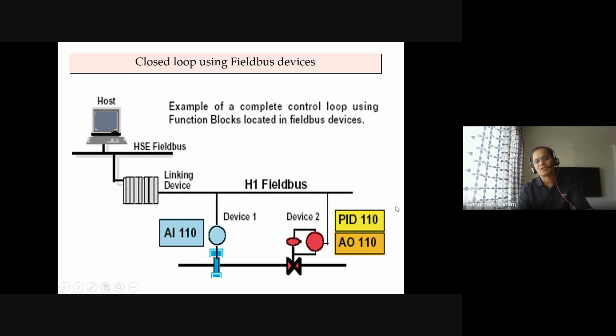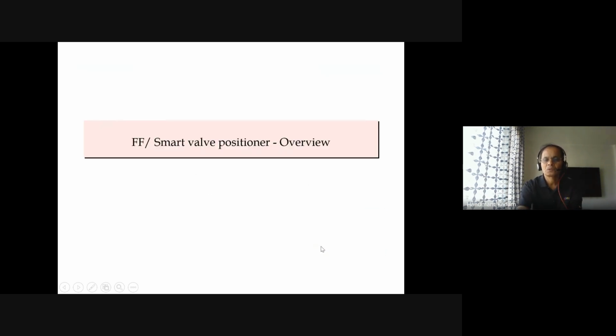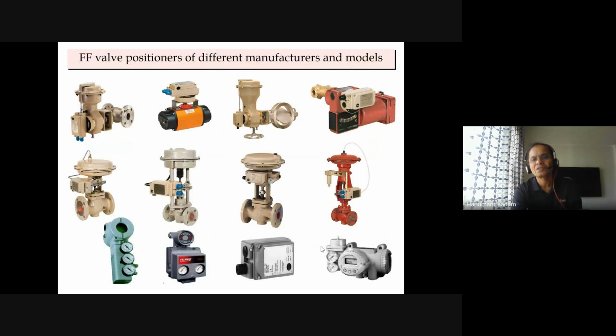The device is here, and you can see this PID and AO block, signal conditioning block, which in the earlier conventional system we used from DCS cards, DCS controller. However, inside the positioner, these blocks are there. I have shown in one of the slides the resource block and transducer block in the positioner. So these are the blocks that are there. These are FF valve positioners, various pictures of positioners from different manufacturers. You see here, this is from Fisher, this is from Dresser, Samson, Smar.